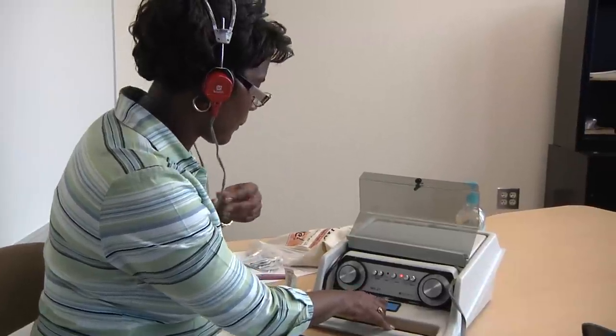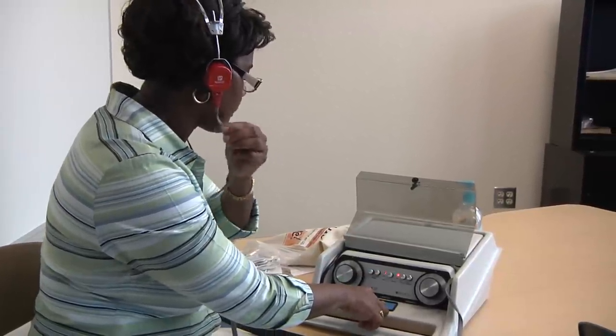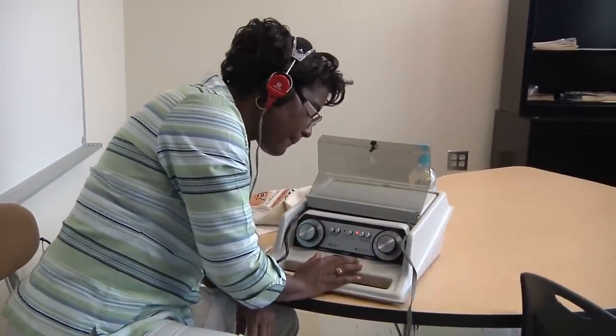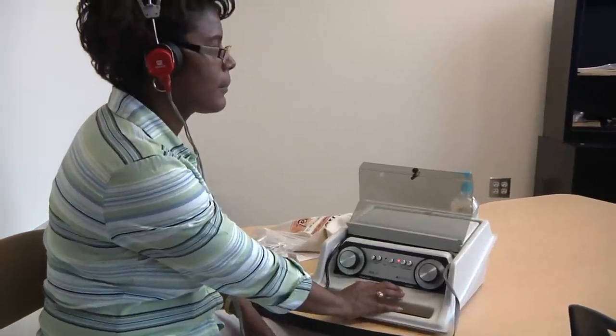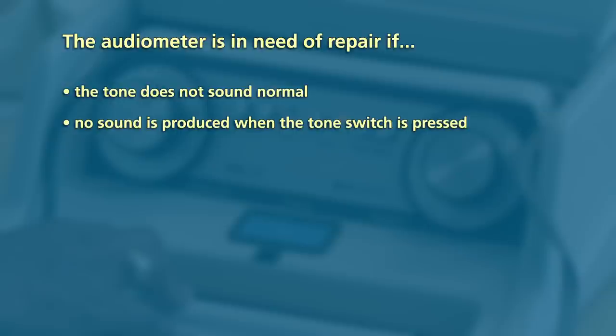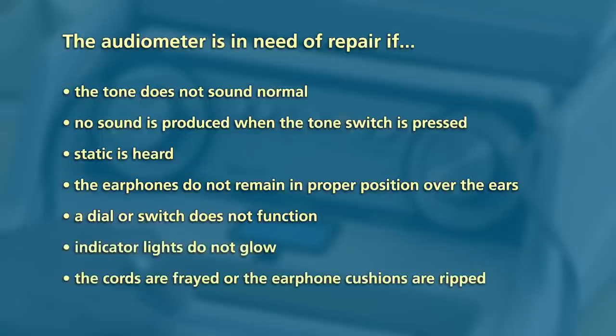With the headset on, push the tone button and move the cords, listening for static or a loose connection. Sit where the children will sit and rest your head and arms in positions you expect the children to sit — listen for sounds conveyed through the table, with elbows resting on the table, head on hands, and also listen for sounds from the chair with your head back against the chair rest to see if vibration from the room may interfere with the test. The audiometer is in need of repair if the tone does not sound normal, if no sound is produced when the tone switch is pressed, if static is heard, if the earphones do not remain in proper position, if a dial or switch does not function, if indicator lights do not glow, or if the cords are frayed or the earphone cushions are ripped.